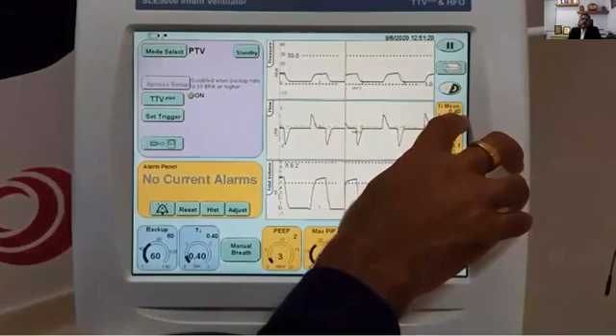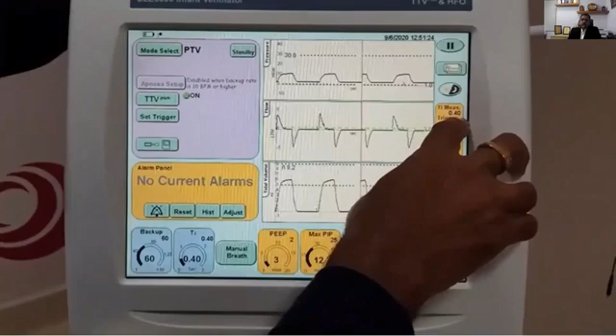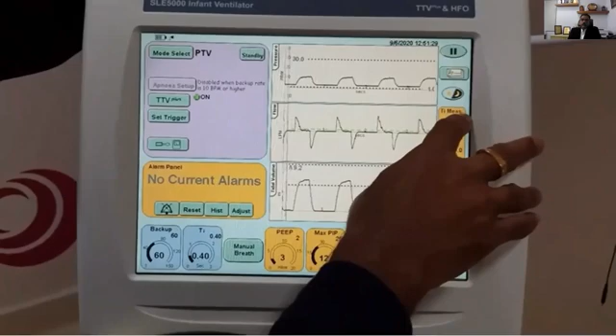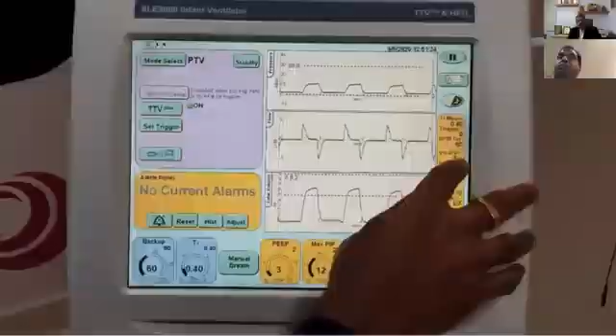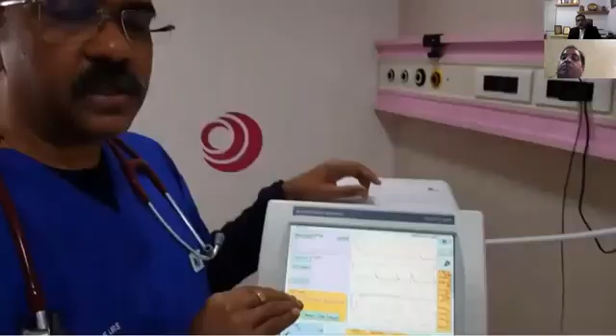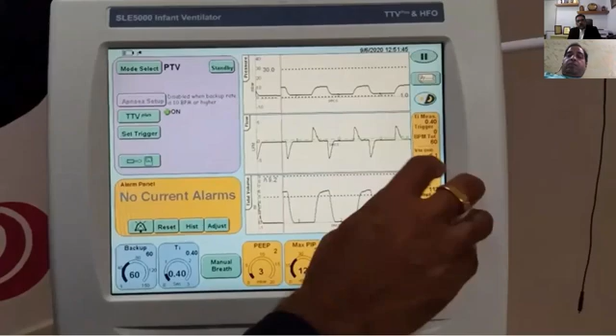One of the things we get here is the trigger, so you will know how many breaths the baby has triggered, the total number of breaths per minute, and the inspiratory time which is kept. And you have the tidal volume: if there is a gross deterioration in the tidal volume, that means there may be a tube block or even a dislodgement of the tube, which causes a drastic reduction in the tidal volume. The minute volume is equally important.